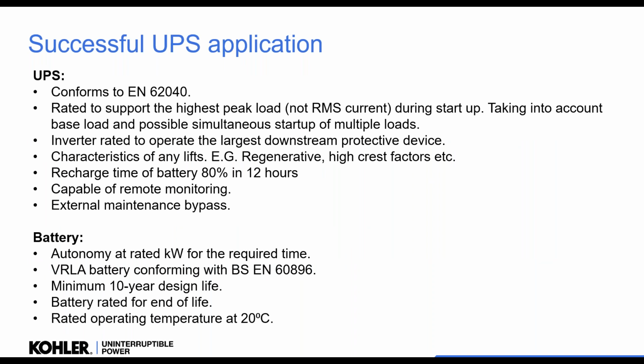We have to specify it, because when you're going to a UPS company, manufacturer, supplier, if you just say I want, let's say, a 30 kVA for an hour, that's what you're going to get. So you need to specify certain things and give certain information to make sure you get the right UPS for the application you're doing. Because if we don't know it's life safety, if we don't know there's motor load, if we don't know we need to trip circuit breakers, that isn't going to be sized in that UPS. So having that specification is very important when you're talking to a manufacturer.